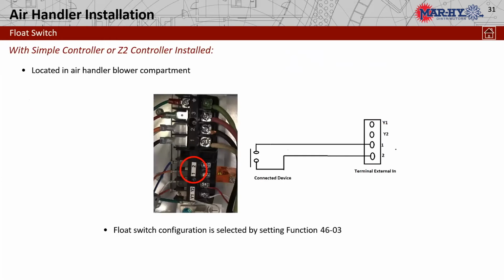Again, we're looking at the low voltage terminal strip on the indoor unit. You can see that 1 and 2 is our emergency stop, or our off switch button, which we would have to program or set up through our function 46 setting number 3. We'll cover these settings a little later on to give you an idea of how this is set up.